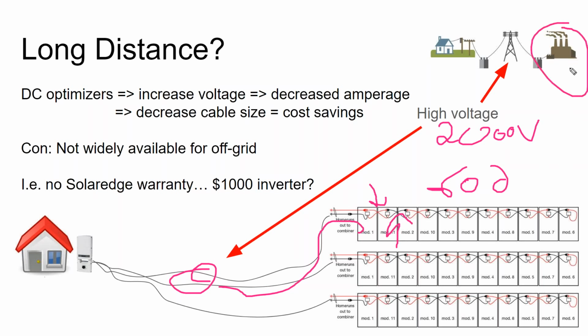And we know from the utility perspective, they go up to incredibly high voltage, over 30,000 volts for distribution circuits, and even more for transmission circuits, to get up into high voltage to transmit that electricity all the way back to your home before they step it down. And so why are they doing that? Why is high voltage used for transmission? Well, the thickness of your cable, the voltage drop is like the second derivative. The first derivative, the primary reason to select cable thickness, is the amperage capacity of the cable.